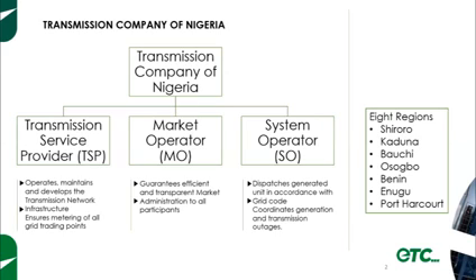The system operator manages the flow of power across this infrastructure. Remember I mentioned earlier that there are set rules in the grid code that decide which generating station fits into the grid, when and how it fits in, and other technical parameters like frequency and voltage. The system operator, through its National Control Center at Osogbo, ensures dispatch of power from the generating stations to the distribution companies.